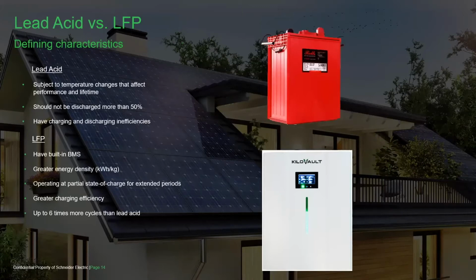So a little contrast, lead acid with lithium iron phosphate. Lead acid is subject to temperature changes that affect performance and lifetime. That's why we ship the battery temperature sensor with the XW Pro, in case you have a lead acid battery in an area that gets cold in winter and warm in summer. If the batteries are in an environment like that, the battery temperature sensor adjusts the charge voltage higher when it's cold and lower when it's warm, because current flow is impeded when temperature decreases and increased when temperature increases.